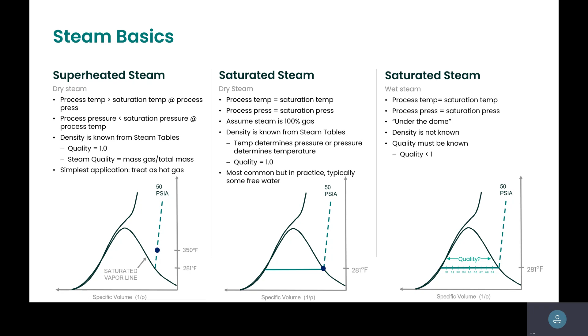So overall, why is steam flow measurement so hard? I'm going to go over a couple of things. Obviously, it's high temperature, over 212 degrees Fahrenheit, but the higher the temperature you go, the more difficult it is. Whatever technology you're using, you have to consider the sensing element. Sampling also needs to be based on the technology you're using. If you don't sample properly, you run into problems. So high temperature really can be an issue.